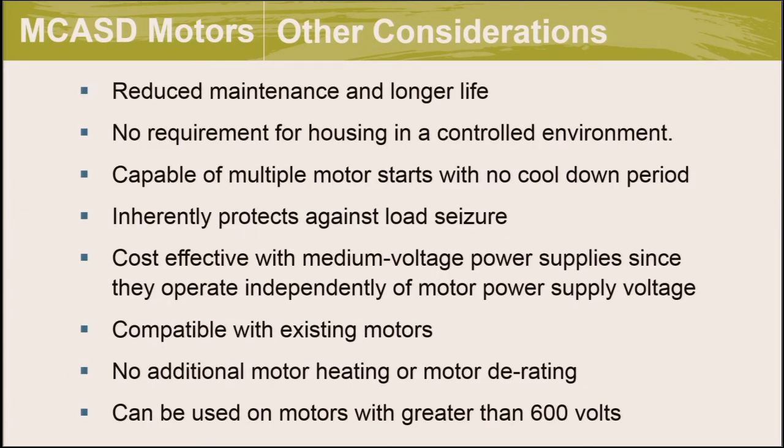The main drawback of magnetic coupling versus VFDs is that it's less efficient — only about two-thirds of the savings. It also cannot drive the load at full motor speed since some slip is needed to create torque, resulting in a 6% to 9% peak flow reduction, requiring potential motor upsizing. It can require 8 to 18 additional inches of space in-line, though a belt-driven mount can help. Benefits include significant energy savings with reduced maintenance, no controlled environment requirement, capability for multiple motor starts with no cool-down, protection against load seizure, and compatibility with existing motors and voltages above 600 volts.